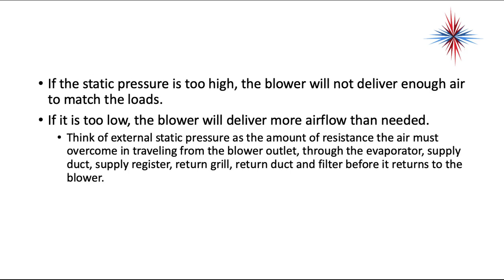If the static pressure is too high, the blower will not deliver enough air to match the loads. If the static pressure is too low, the blower will deliver more airflow than needed. Think of external static pressure as the amount of resistance the air must overcome in traveling from the blower outlet, through the evaporator, through the supply duct, through the supply registers, and on the return side through the return grill, return duct, and filter before returning to the blower.